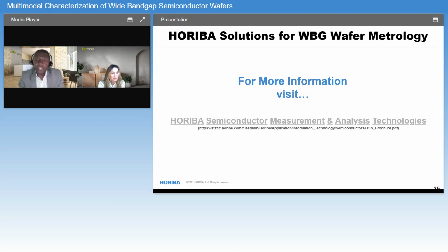No. I think behind that question is maybe a concern about distortion in the beam, because when you're scanning the beam, you're tilting the beam basically. I think that's the concern, but no, that shouldn't be an issue. Of course, the range of rastering is calibrated to basically eliminate those distortions.